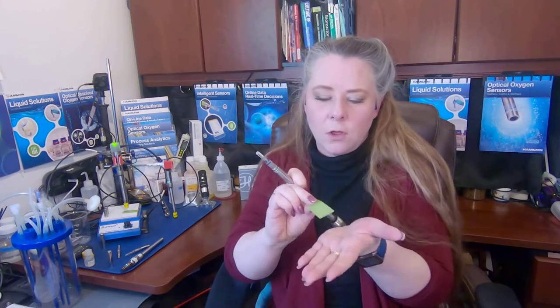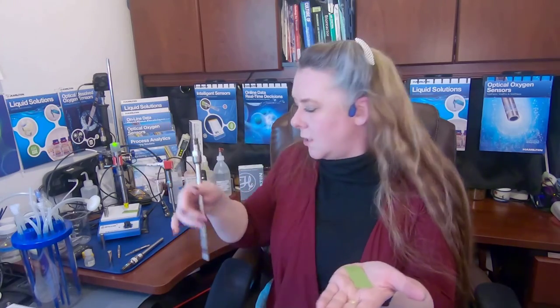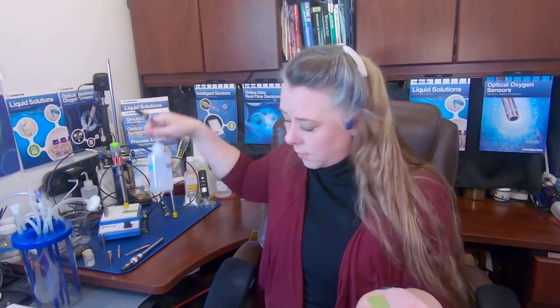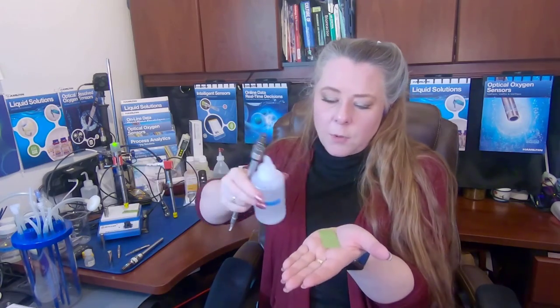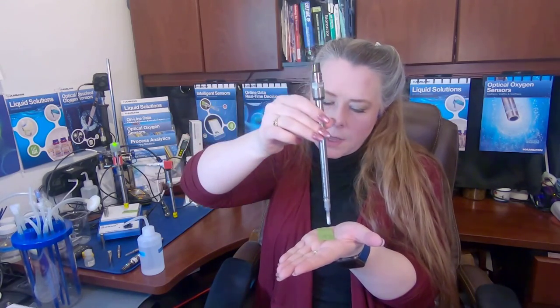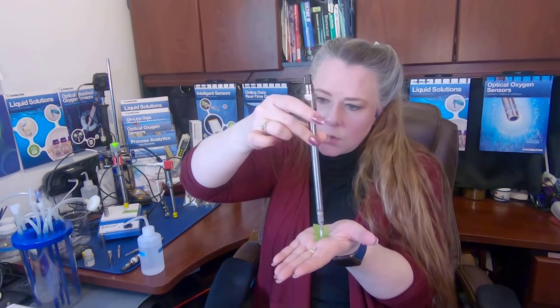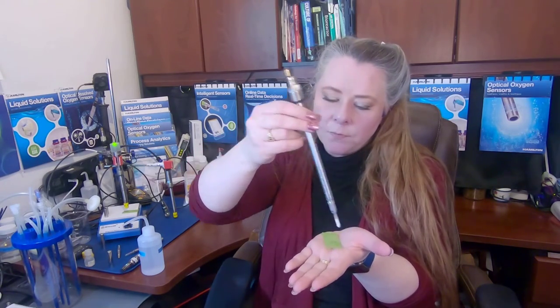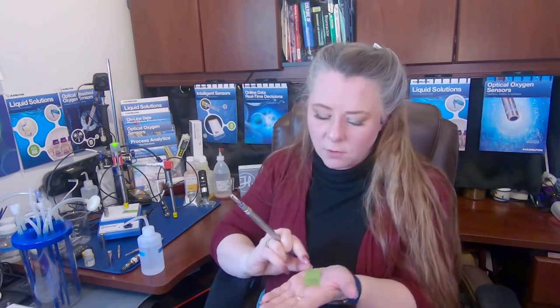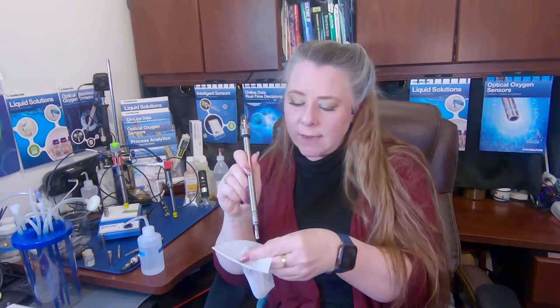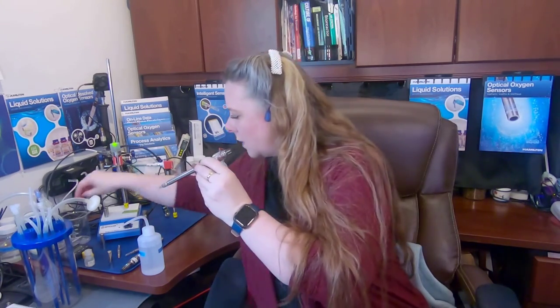So in the palm of your hand, gloved, I just have water, so don't worry about what I'm doing here, but you usually have other stuff on yours. You put just a drop of water and you use the palm of your hand, not a hard surface, because you want some give, and you put the probe in and you twist it 20 to 30 times. All that does is it removes any oxidation that may have coated your platinum. And at the end of that, this is reusable many, many times. And then you can just very lightly blot the end or rinse this off.